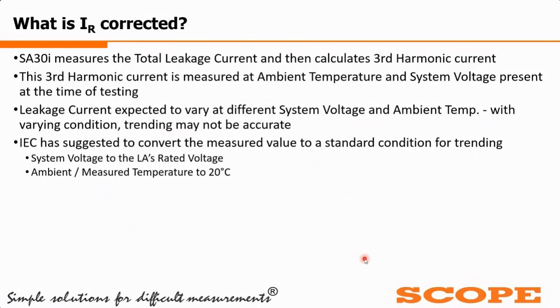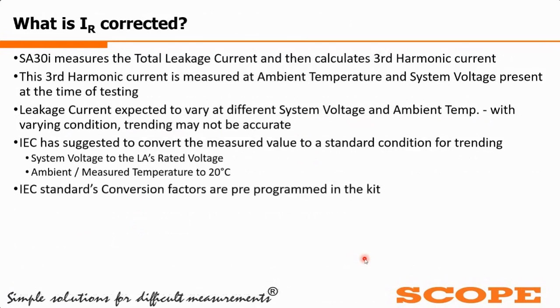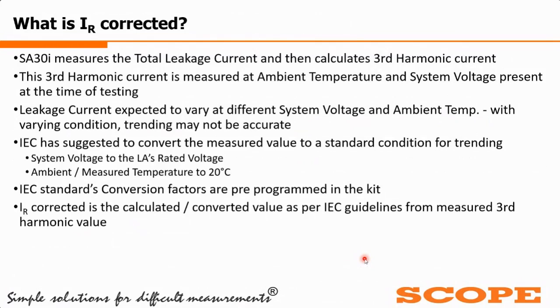So we need to take cognizance of the applied voltage and take it to the extrapolated value at the rated voltage, and take the measured ambient temperature and extrapolate it to a temperature of 20 degrees. What could be the value? IEC has given those graphs. IEC standard conversion factors are already programmed in our kit. So IR corrected is the automatically calculated or converted value, as per the IEC guidelines, from the measured third harmonic value to reach the IR, meaning the resistive value.